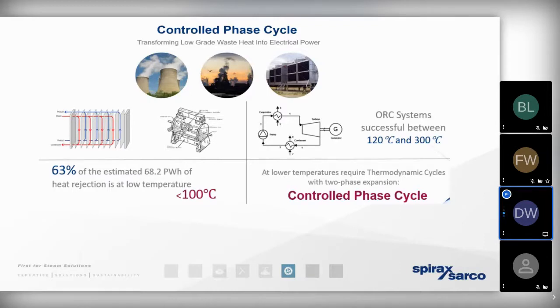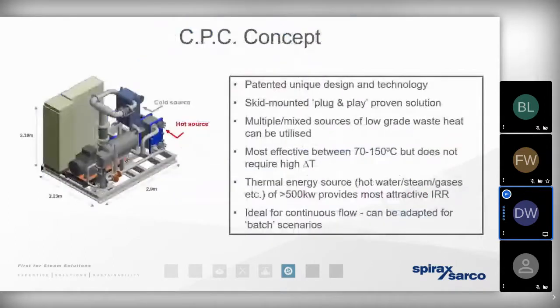So a traditional organic Rankine cycle based heat recovery system is only going to be able to make use of temperatures in excess of 120 degrees or thereabouts. Whereas a controlled phase cycle, or a CPC, can make use of the energy in waste or effluent at temperatures as low as 70 degrees. Now, obviously, the higher the temperature, the greater the rewards are going to be. But if we can drop the temperature of the waste to 70 degrees or below and utilize that energy in some other form, we're going to have significant benefits. And that's where the CPC, or the controlled phase cycle concept, really comes in.